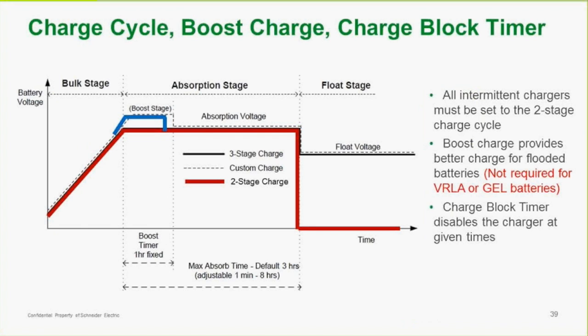This graph is a typical charging graph. As you can see, we have a bulk stage followed by an absorption stage, followed by a float voltage. The three-stage charge is the black line. The two-stage charge is the red line, where you don't actually go into float. It just goes back to possibly supplying power to loads. There's a little boost section shown here. That's normally used for flooded batteries, which are becoming more and more rare. We would not use a boost for VRLA or gel batteries.